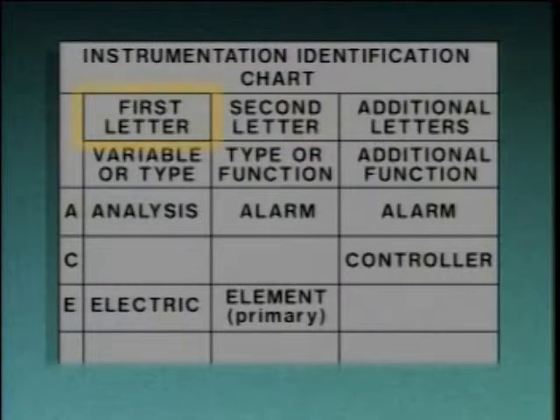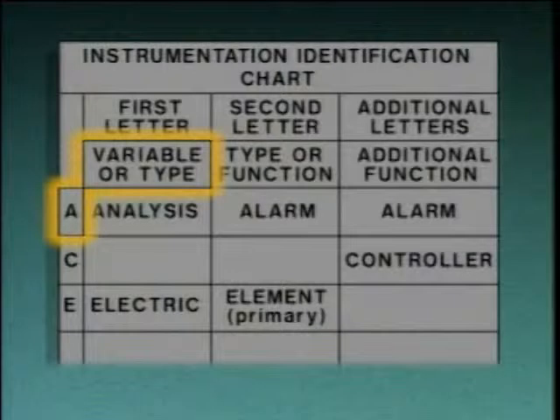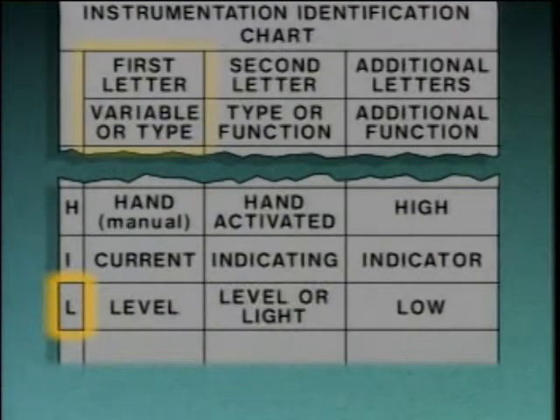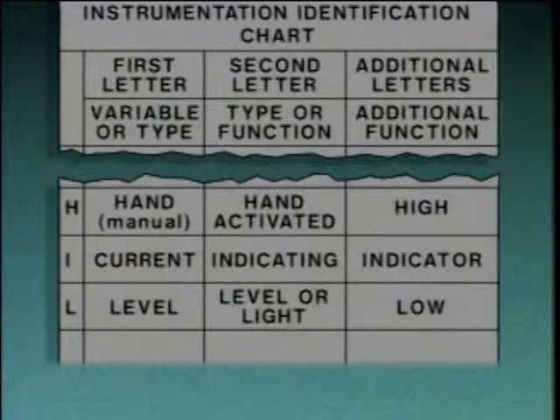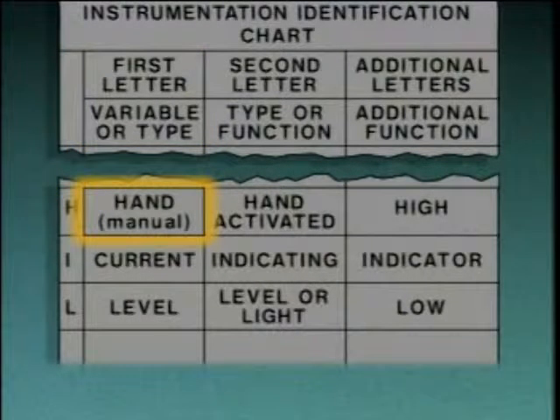In most cases, the first letter in the symbol designates the process variable associated with the symbol. For example, A as the first letter indicates that the instrument performs an analysis, such as a pH or density measurement. An L as the first letter means that the instrument measures level. If the first letter doesn't indicate a process variable, its meaning is usually explained on the chart. For example, H as the first letter stands for hand and means that the instrument is operated manually.